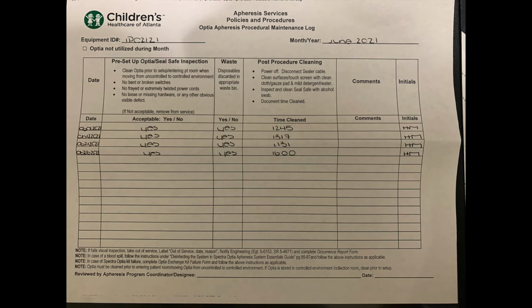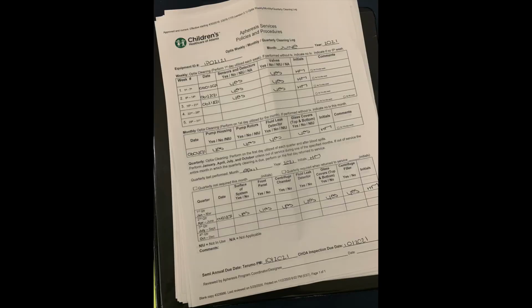If the machine has frayed or twisted power cords, it would be removed from service. Post-procedure cleaning is similar to pre-collection, including inspecting and cleaning the Seal Safe. Waste is disposed within a labeled red biohazard bag and disposed in an appropriate waste bin. Verification of cleaning logs is done prior to collection, ensuring the weekly, monthly, and quarterly cleaning logs are up to date. All cleaning logs are found on the back of the Spectra Optia.